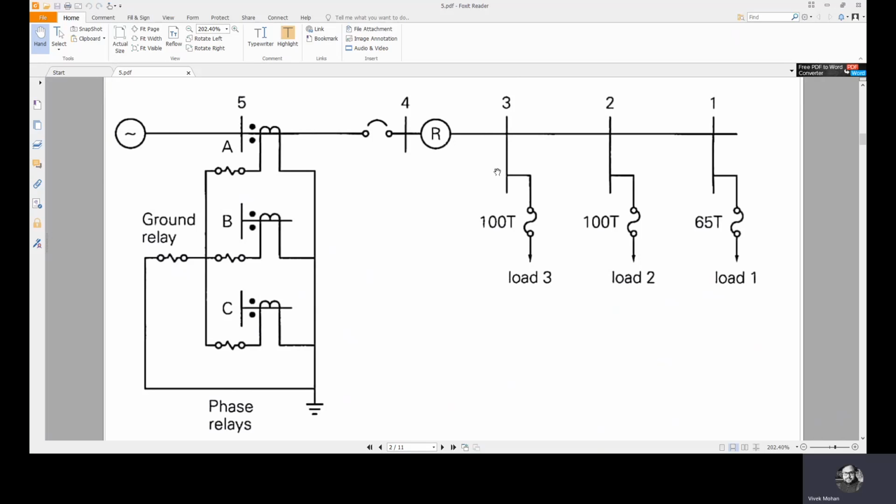I'll give you an example here. Suppose I have a fault beyond this particular fuse, which is temporary, momentary. So this recloser will reclose some number of times. We will define the sequence later, but it will have some fast and slow, or fast and delayed, reclosures until this fault is cleared.